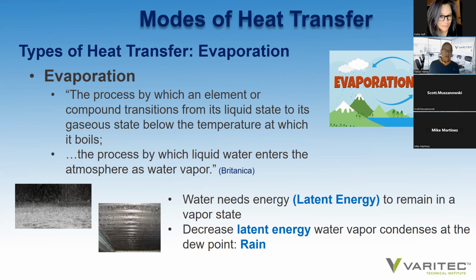The reason why HVAC systems are fundamentally a heat or energy transfer methodology, we can actually control water vapor and humidity in a building by controlling the energy. If we can bring the water vapor in a building to dew point by reducing temperature to a sample of air with high humidity content, that water vapor cannot be sustained in a vapor state and will condense in condensate pans at a cooling coil. And that is how building humidity is controlled by bringing the air that's being conditioned to dew point to wring the water vapor out into a liquid state where it can be evacuated from a building.